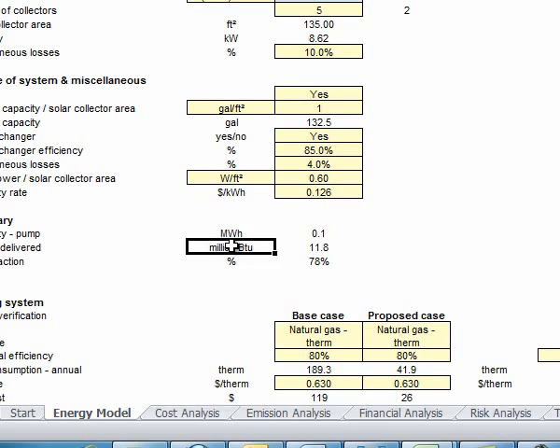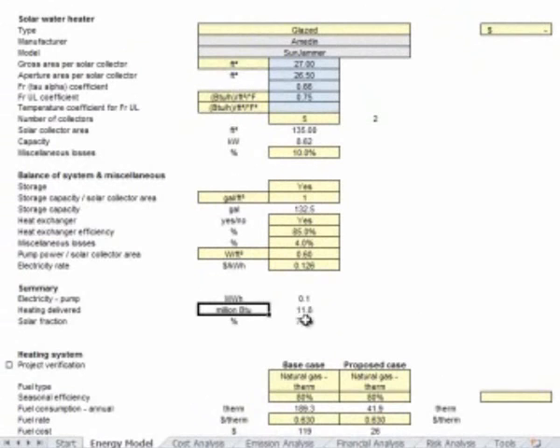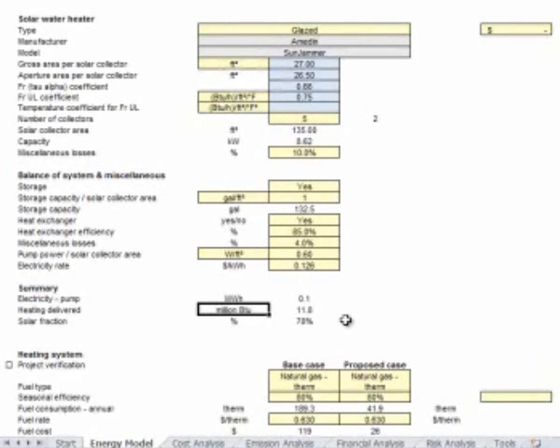That gives me an electrical summary of I'm saving about 11.8 million BTUs. If I move that decimal place one to the right, that will give me therms. That's just a very rough equation to give me therms. So 118 therms of energy will be saved.